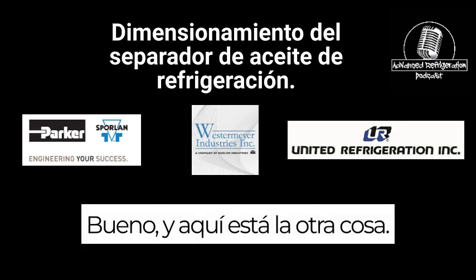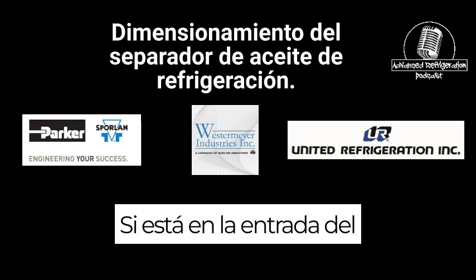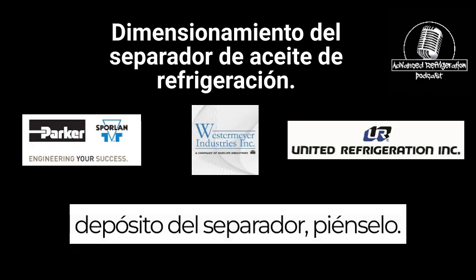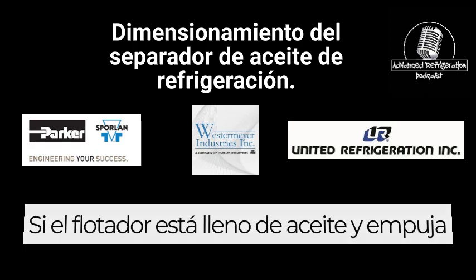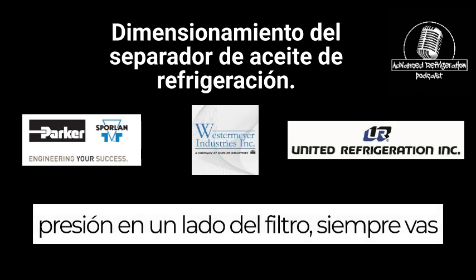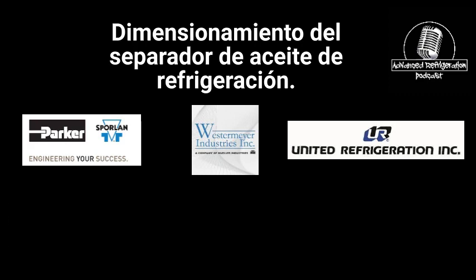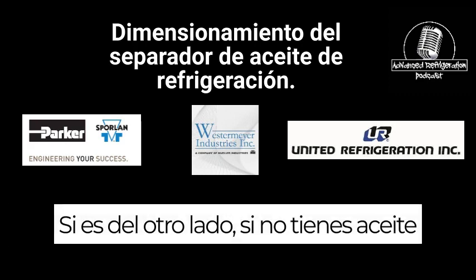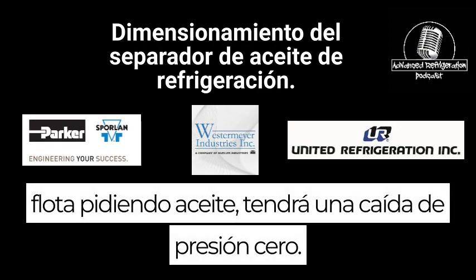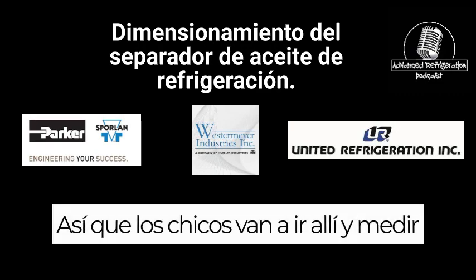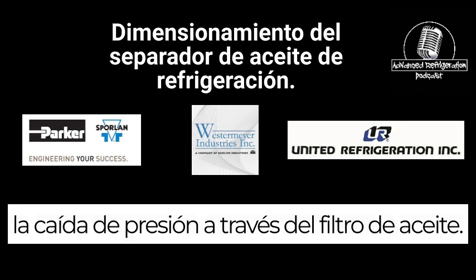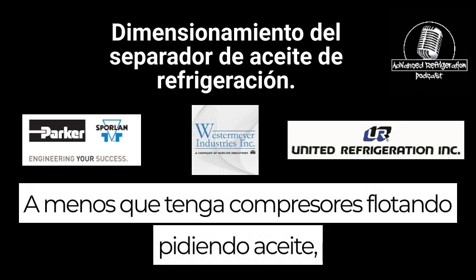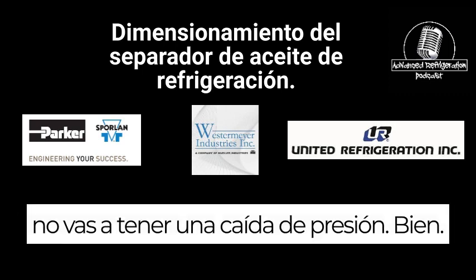Well, and here's the other thing: if it is on the inlet to the reservoir from the separator, think about it. If the float is full of oil and it's pushing pressure on one side of the filter, you're always going to have a measurable pressure drop on it. If it's on the other side, if you have no oil floats calling for oil, you're going to have zero pressure drop. So a guy's going to go measure the pressure drop across the oil filter, and unless you have a compressor float calling for oil, you're not going to have a pressure drop.